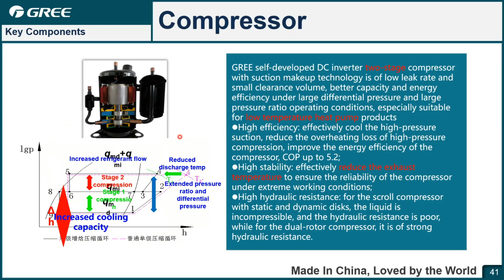So for the compressor, VERSATI 3 used the two-stage compressor. Two-stage with the EVI function. So actually you can see here, even the ambient, the evaporating temperature is very cold. In a very cold ambient, for ordinary discharge temperature is very high. However, if there is a EVI technology, it can reduce the discharge temperature to keep the unit run very well in a very cold ambient.